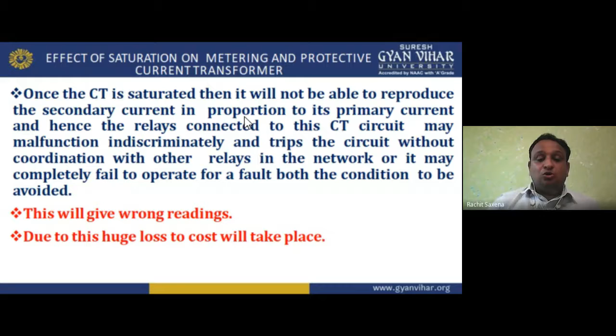That is a wrong or adverse thing for us, because the circuit breaker has to isolate the circuit or open the circuit when the fault occurs, when the CT trips the coil. And if the current transformer is not working properly, malfunction will occur. It may trip indiscriminately, without coordination with other relays in the network, or it may completely fail to operate for a fault. Both conditions have to be avoided. This will give wrong readings and cause huge loss in cost.